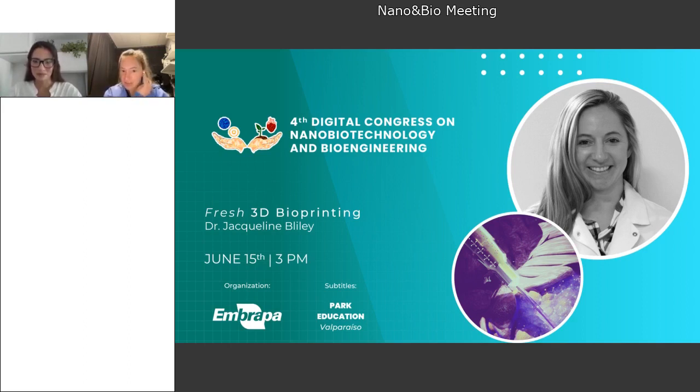So there are definitely a lot of challenges. One you can think about, especially if we're looking at patient-specific implants, is taking either an image from a patient and then creating a patient-specific model. The first challenge is actually validating that it does fit with the patient, that it is exactly what we intended to print. And that's usually done by process gauging. We've done a lot of that in our lab. We have pretty accurate reproducibility among our prints, plus or minus 20 microns, depending on the size of the needle that we're using to print our structure, which ultimately determines the resolution of the final print. But that's one challenge.